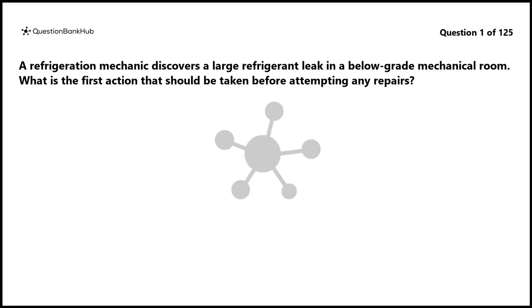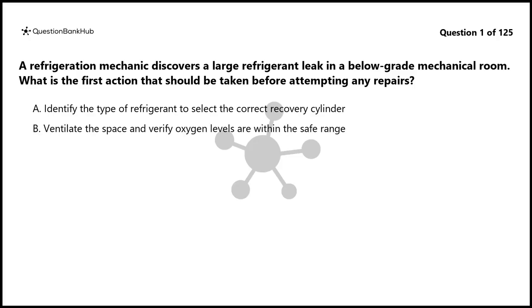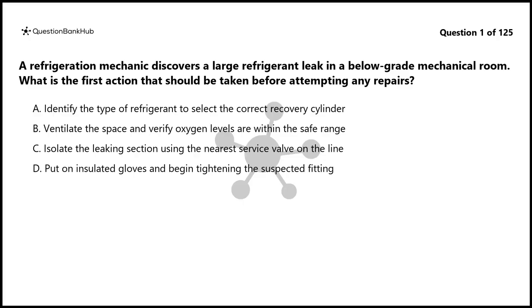Question 1. A refrigeration mechanic discovers a large refrigerant leak in a below-grade mechanical room. What is the first action that should be taken before attempting any repairs? A. Identify the type of refrigerant to select the correct recovery cylinder. B. Ventilate the space and verify oxygen levels are within the safe range. C. Isolate the leaking section using the nearest service valve on the line. D. Put on insulated gloves and begin tightening the suspected fitting.